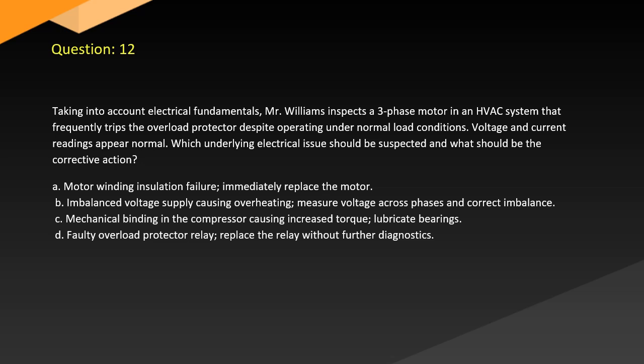A. Motor winding insulation failure. Immediately replace the motor. B. Imbalanced voltage supply causing overheating. Measure voltage across phases and correct the imbalance. C. Mechanical binding in the compressor causing increased torque. Lubricate bearings. D. Faulty overload protector relay. Replace the relay without further diagnostics.